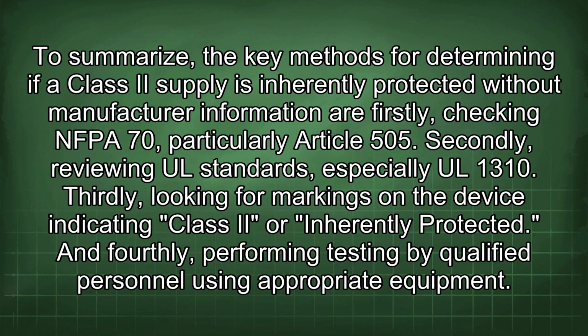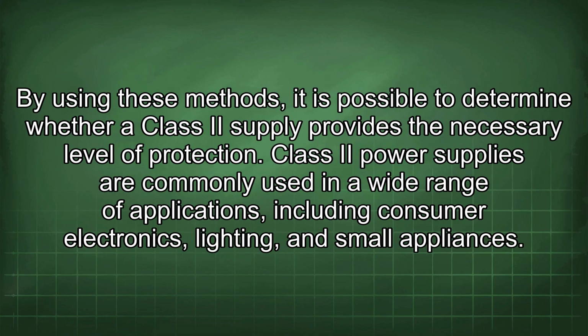To summarize, the key methods for determining if a Class II supply is inherently protected without manufacturer information are: firstly, checking NFPA 70, particularly Article 505. Secondly, reviewing UL standards, especially UL 1310. Thirdly, looking for markings on the device indicating Class II or inherently protected. And fourthly, performing testing by qualified personnel using appropriate equipment.